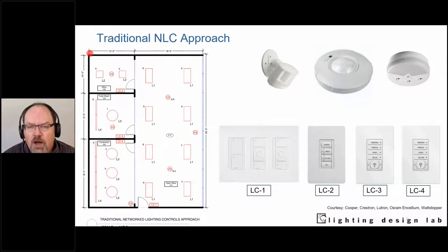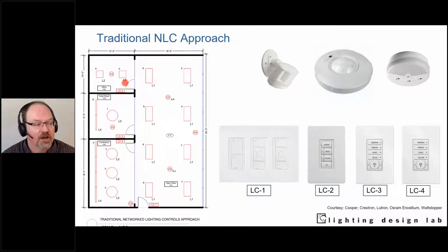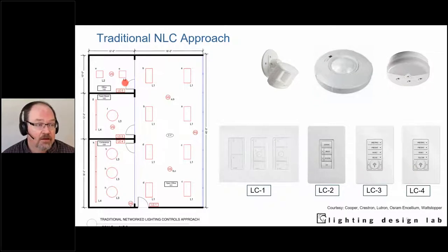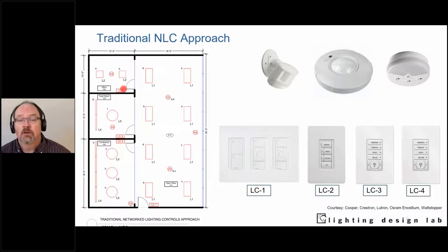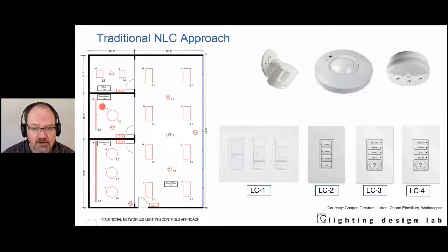Back to the private office: we have a vacancy sensor and defined control zones. In the team room, we have a decorative pendant and a wall washer — those are on different control zones so they can be controlled independently, with one vacancy sensor controlling both. In the conference room, we have three decorative pendants on one control zone and one linear zone for the wall washer. You can also put each pendant on its own zone — as long as you have at least the two control zones required.